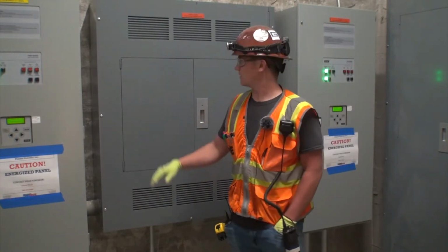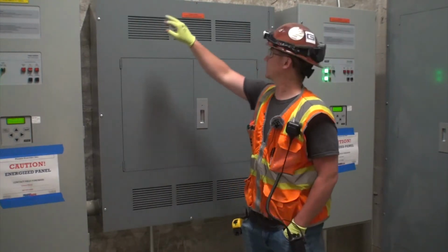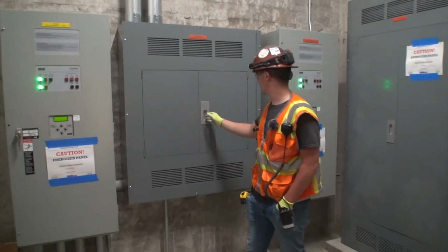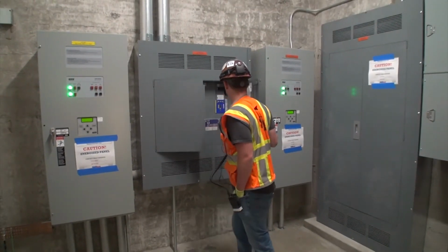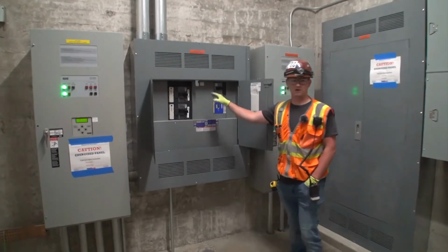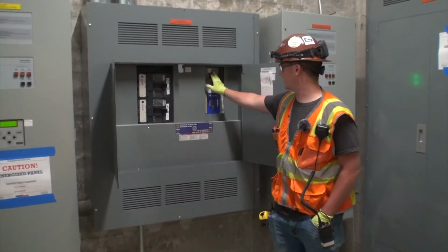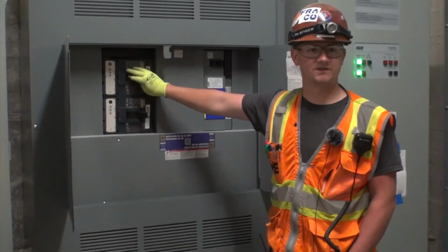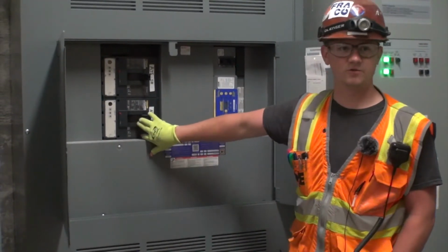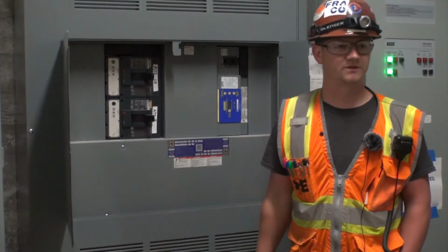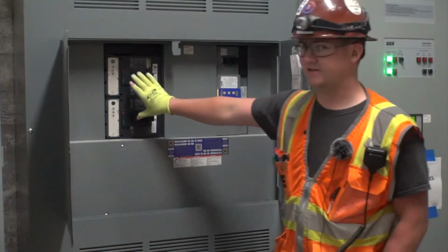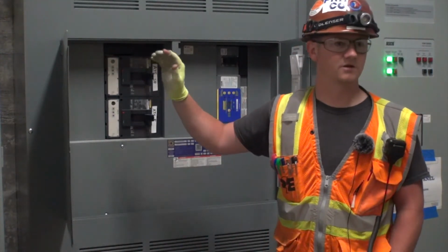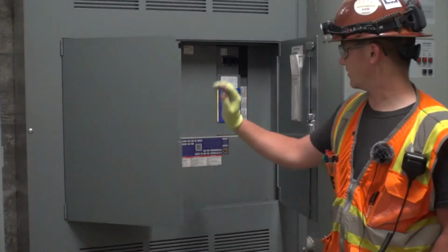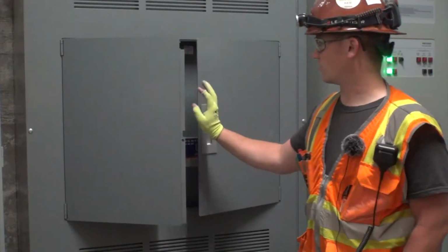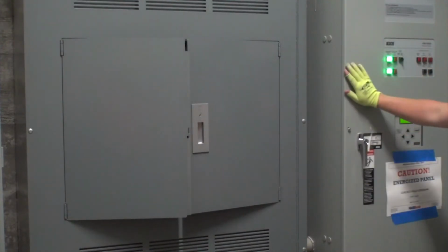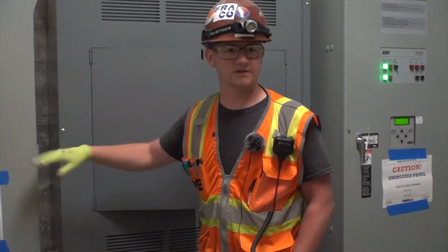Okay, so what we have here is the generator outside. That comes in through these two 4-inch pipes, into here. All these breakers need to be on for the system to work correctly. So you have a breaker here, a breaker for SB, which is standby power, and a breaker for E, which is emergency lighting, the emergency side. Each of these, anytime the generator comes on, they'll both come on. Unless the breaker's off, they'll both come on. So from there, they come into here, through both, to each transfer switch.